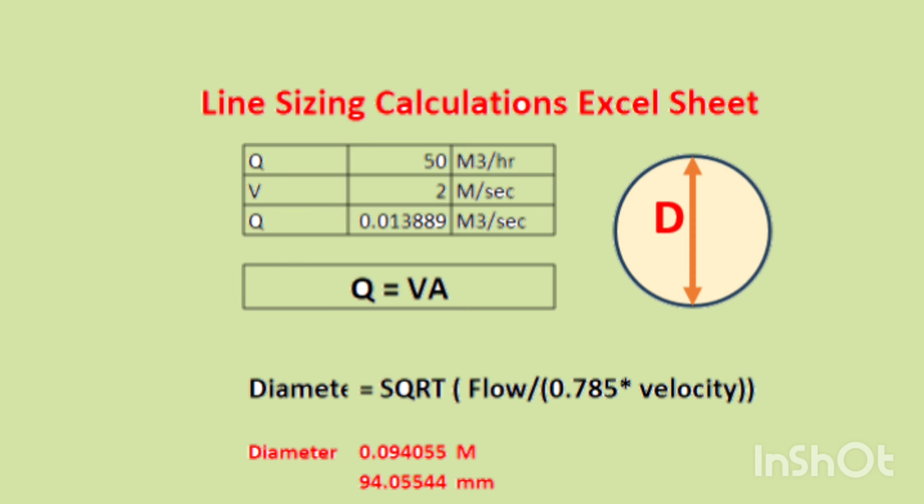If the pressure drop matches your requirement, then our considered velocity of 2 meters per second is OK, and our diameter calculation is also OK. If the required pressure drop and calculated pressure drop have a difference, then we have to rearrange this velocity, whether it is 2.5 or 1.5, depending upon the calculated pressure drop.